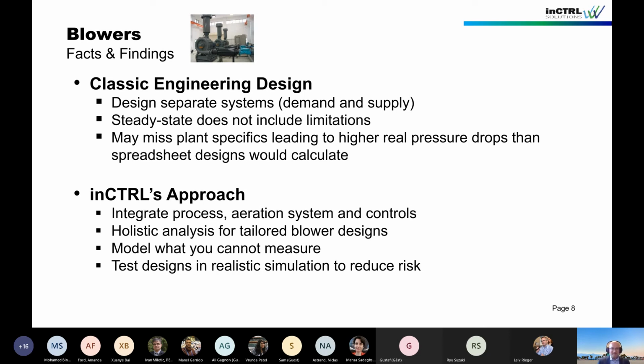So the approach we've been using with this integrated model, where we integrate the process, aeration system, and controls all together in the same model, allows for a holistic analysis, and this allows for more tailored blower designs. And one of the big things is that you can model things that are typically hard to measure, because you may not have sensors everywhere, and if you have a model of the system, you can essentially model things that are hard to measure.